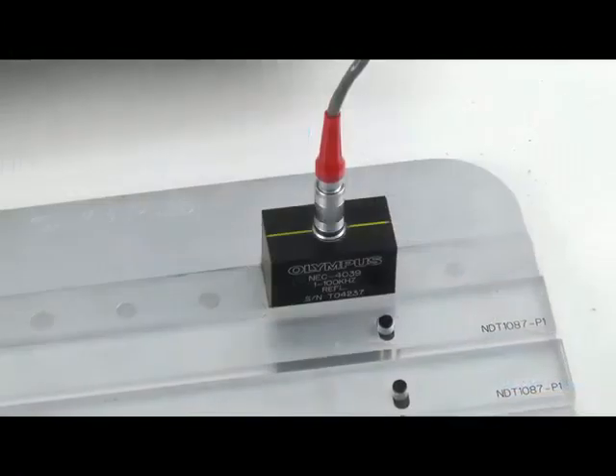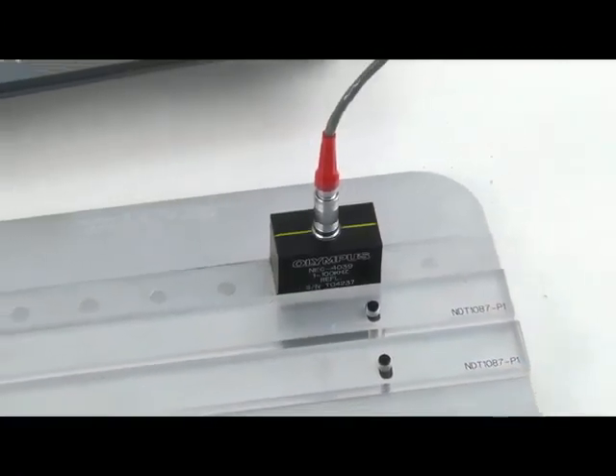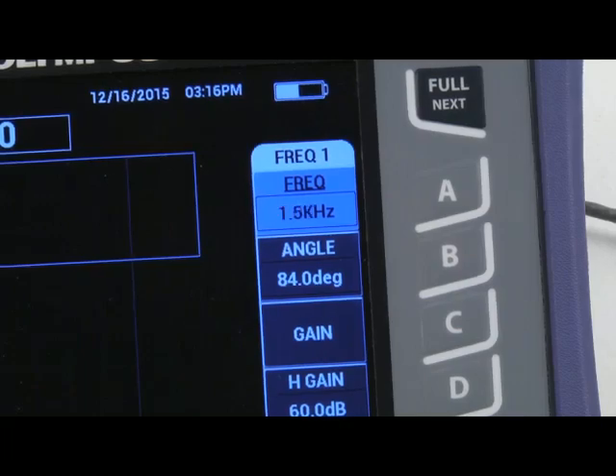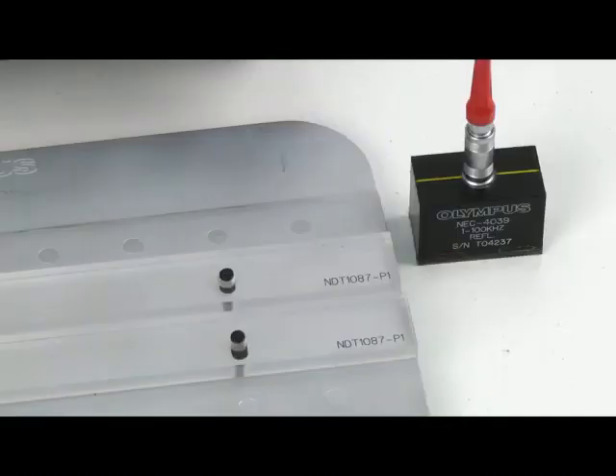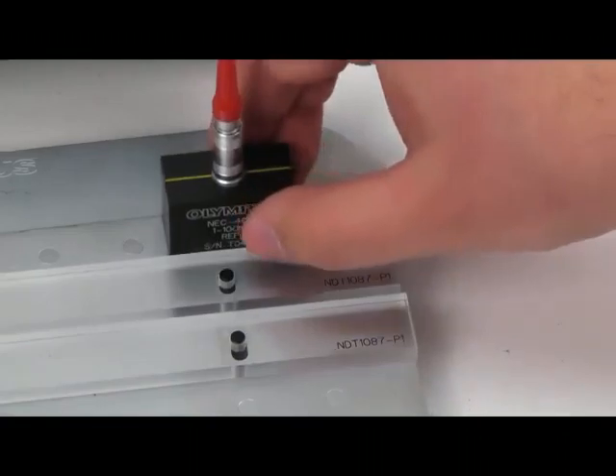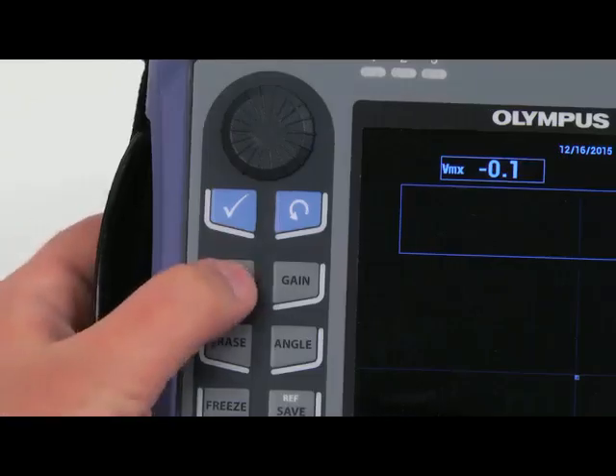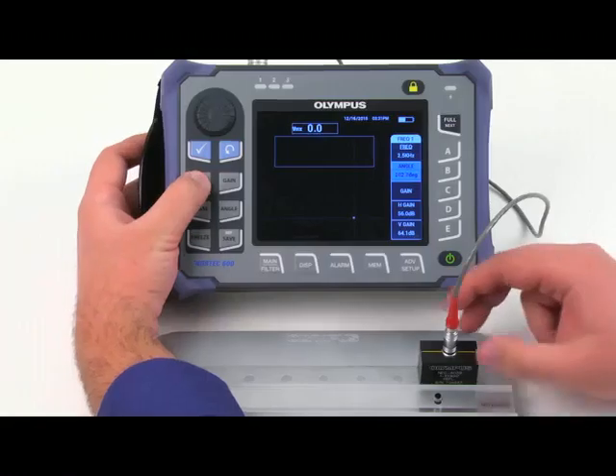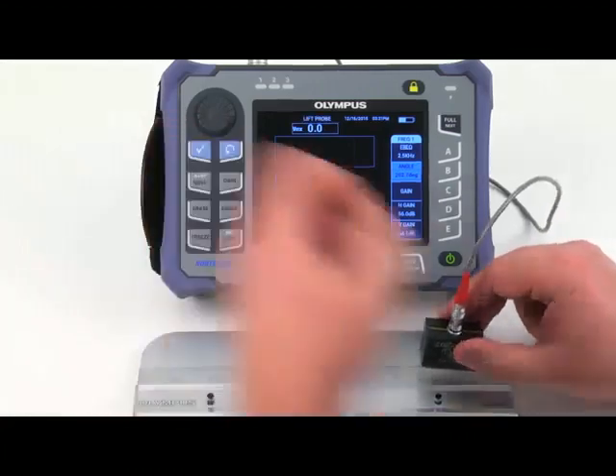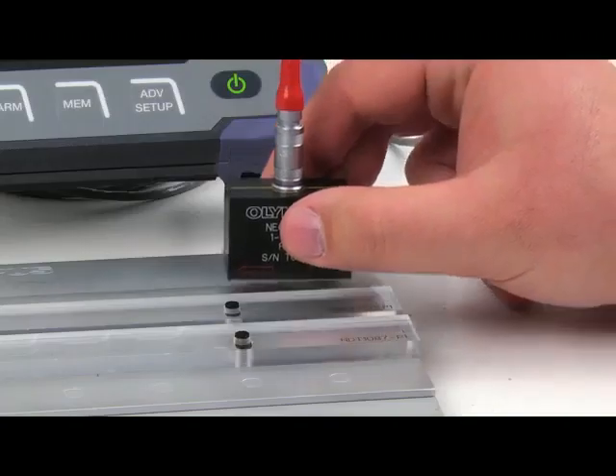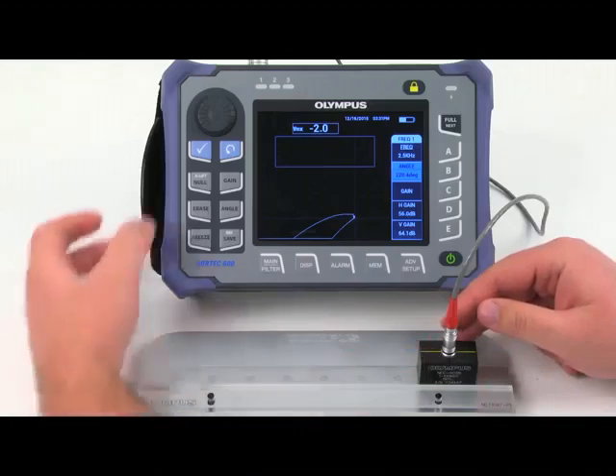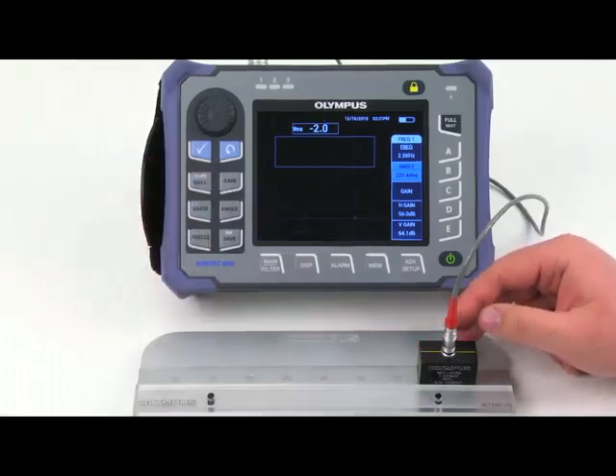Another way to inspect subsurface cracks is to use a sliding probe. Set your frequency to 2.5 kHz. Place the sliding probe on a defect-free area of the calibration standard. Press and hold the null key. This will activate the auto liftoff function. When you hear the beep, lift the probe. Place the probe back on the defect-free area and press null.